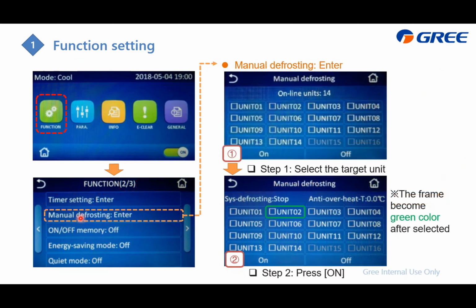Next is manual defrost, which is to force the chiller to defrost. When you enter this one, we'll go to this page. The first step is to select which chiller. In this case, for example, we just select unit 2 and tick it.